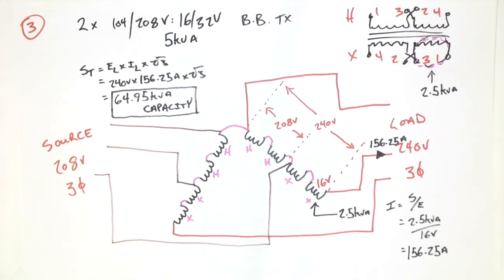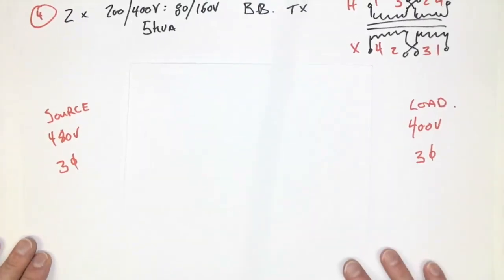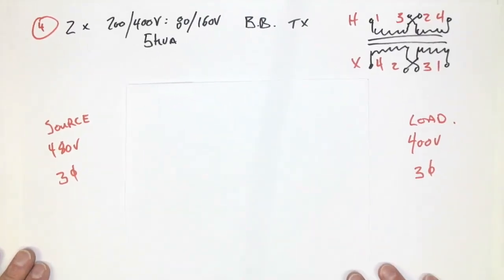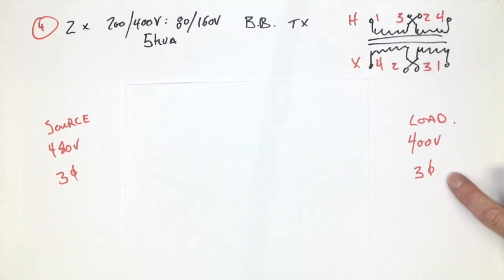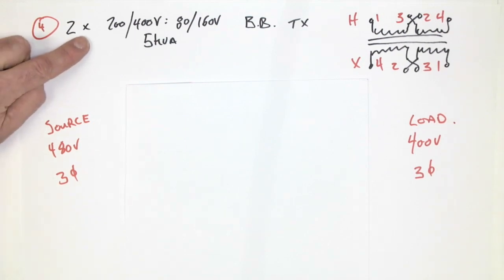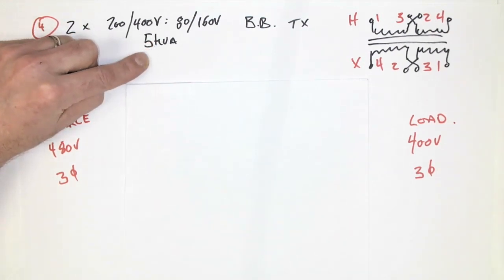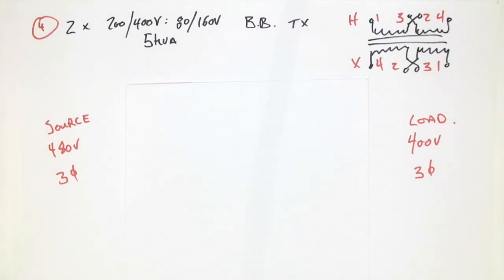All right, well, let's do one last example. And this one again is going to be an open delta. So here's our open delta. We've got a 480 volt three-phase source, a 400 volt three-phase load, and we've got two 200/400 by 80/160 5 kVA buck boost transformers.